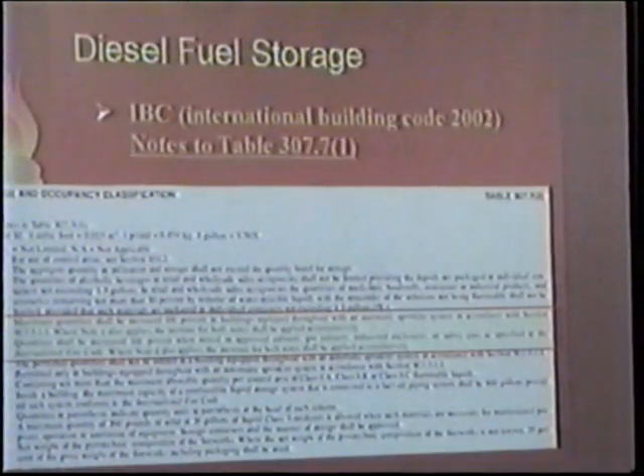Brooklyn Park caught it on a warehouse job a number of years back, and they were okay. They didn't make them wall it off. They made them mark the tank fuel gauge so that the delivery driver would know not to fill it more than X full. Would that be a separate permit by chance, or is that for that storage tank room? I have no idea.